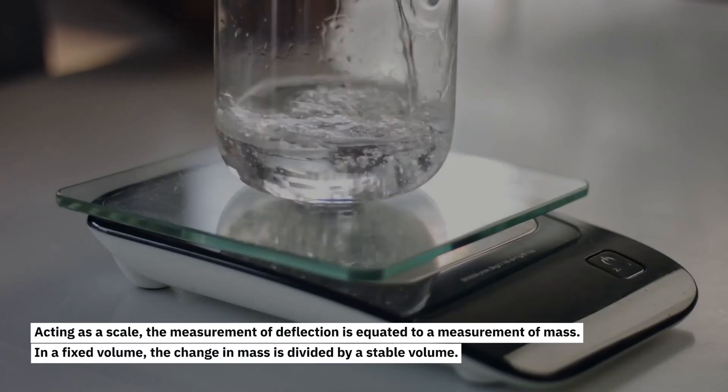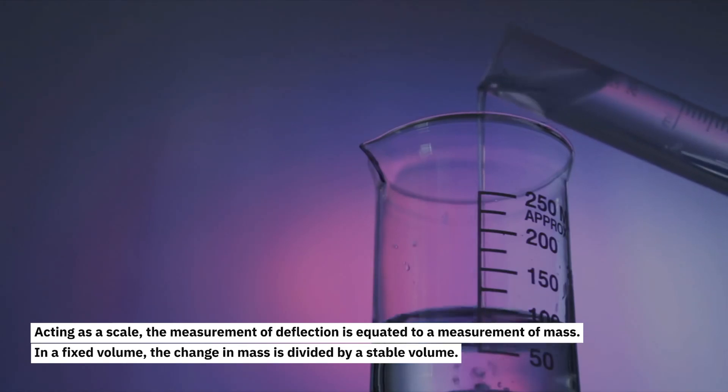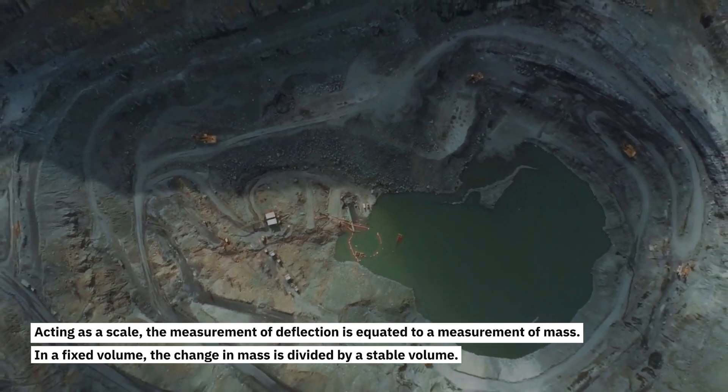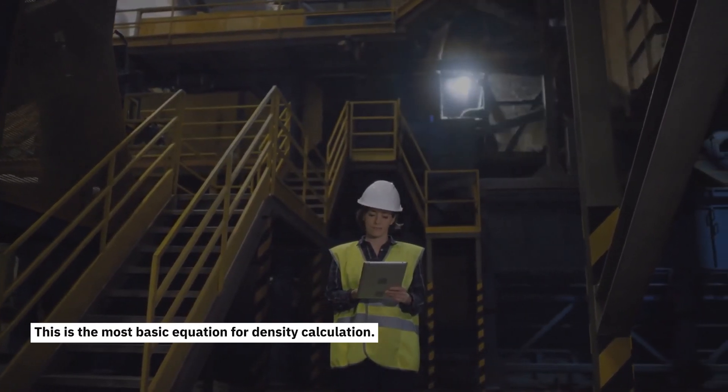Acting as a scale, the measurement of deflection is equated to a measurement of mass. In a fixed volume, the change in mass is divided by a stable volume. This is the most basic equation for density calculation.